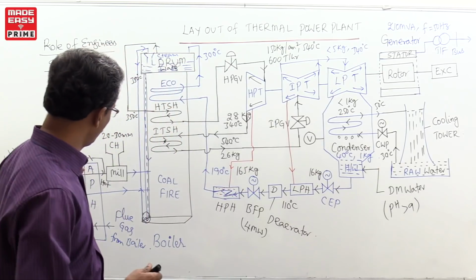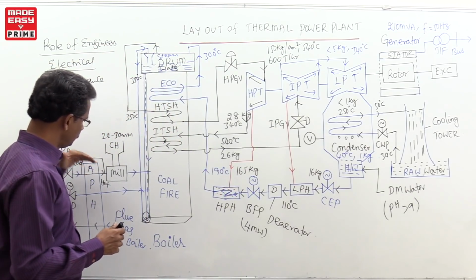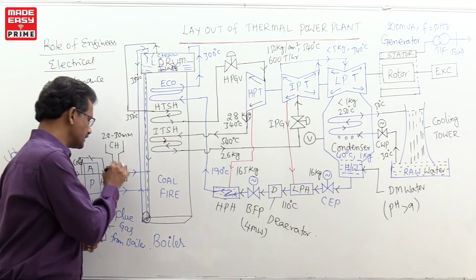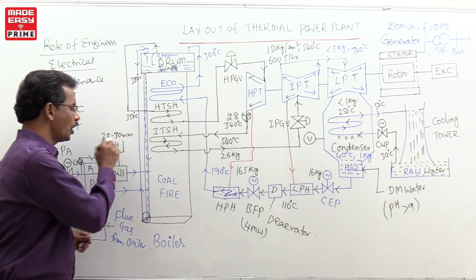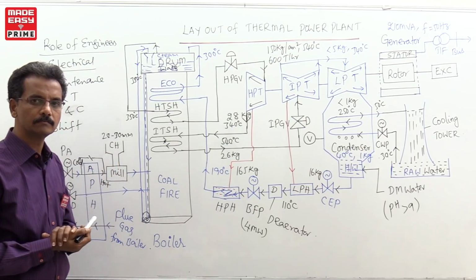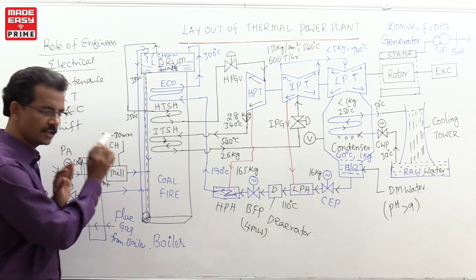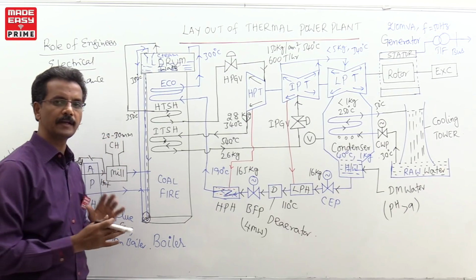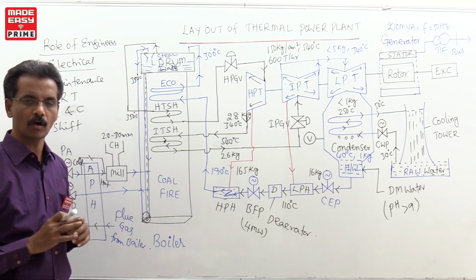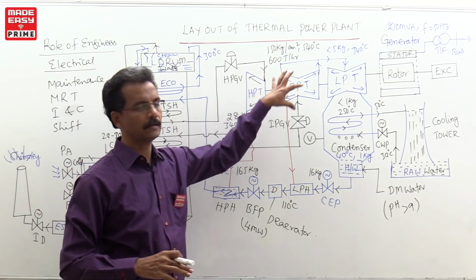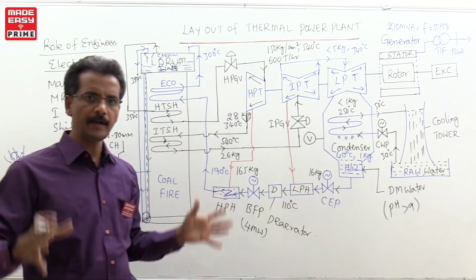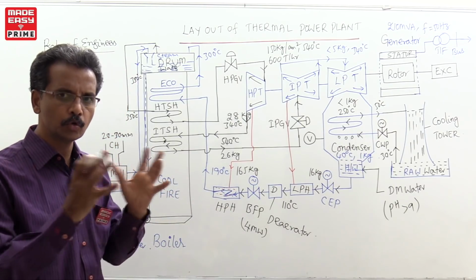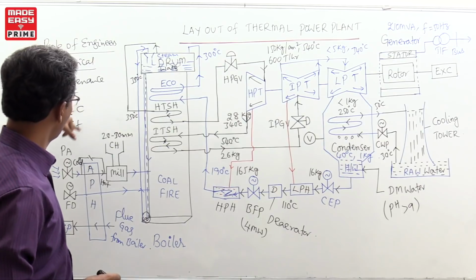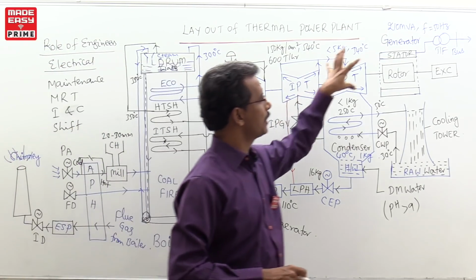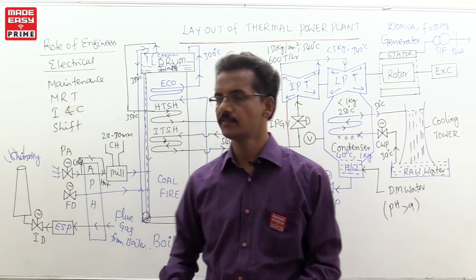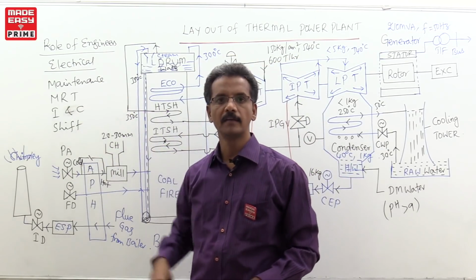Like I am sending coal from the mill to the boiler. From where is the mill getting the coal? From the coal hopper. Whether the coal hopper is working properly or not, they have to check. So the common auxiliaries engineer will go and inspect periodically whether it is working healthily or not. Similarly, turbine as well as generator. So this complete group of engineers coordinates all the departments so that proper output is possible. These are some of the roles of our electrical engineers.